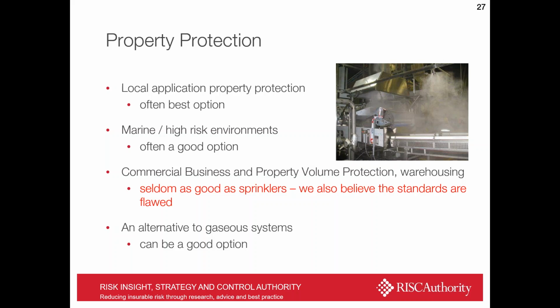In the marine environment, we have very well-sealed compartments. The fuels that they use generally lead to very large instantaneous fires, and it all plays to the strengths of Watermist, as we've seen, as being very effective. The grey area, I would say, comes when we look at commercial business and property volume protection. These are really the domain where sprinklers are used, warehouse storage, and the like. And this is where we see most challenges, and often we see them putting in facilities where really sprinklers would have been a better choice after all. And I'll go on to some of the reasons for that later on.